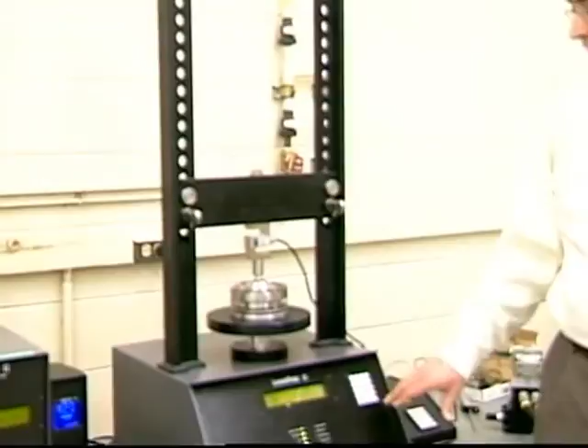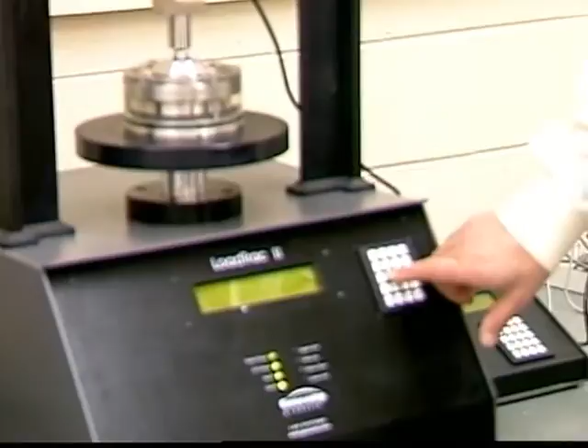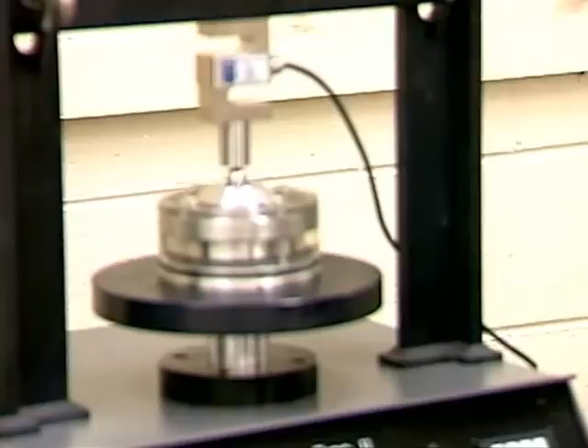It says 1, 2, 2 is position, so I go to position. And now I'm into a sub-menu that gives me the options of raising the platen, lowering the platen. And what I'll do, I do 2, lower, and enter. So now it's going to lower my platen, so I can release the load. I'll make sure that once the load is released, I just hit escape key to stop it.